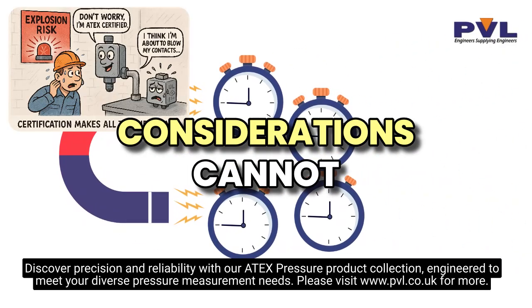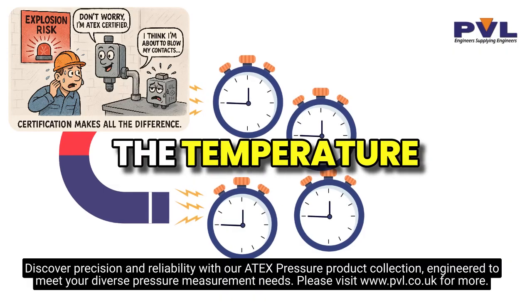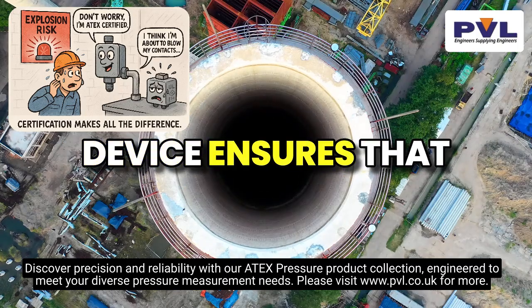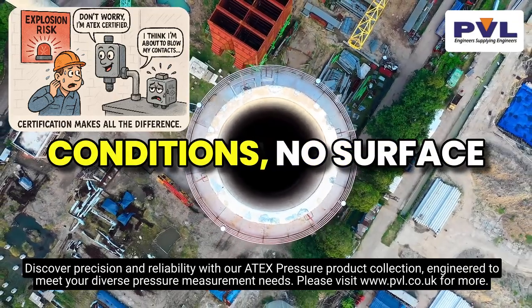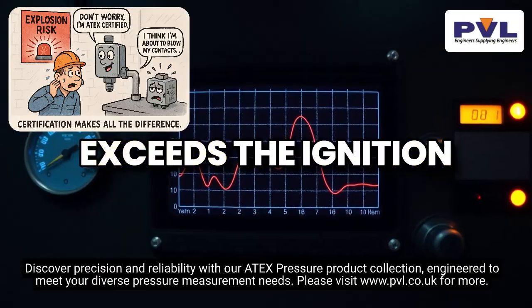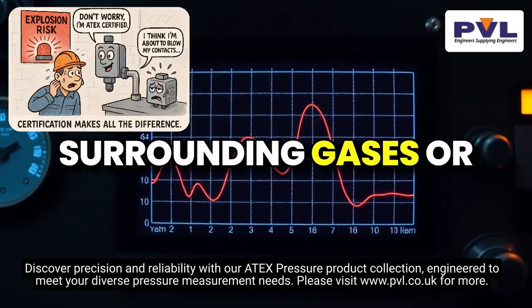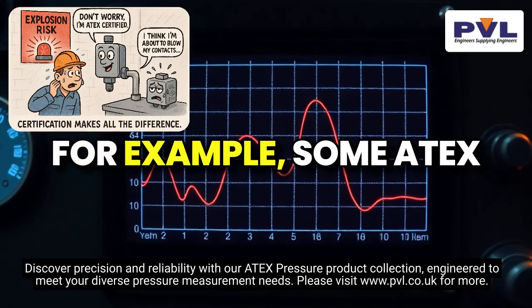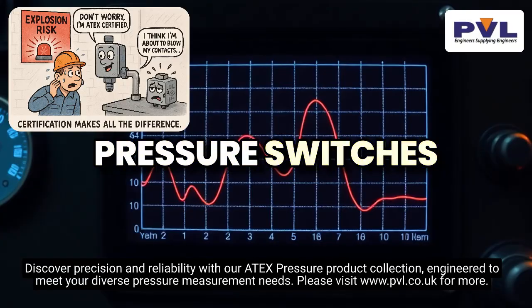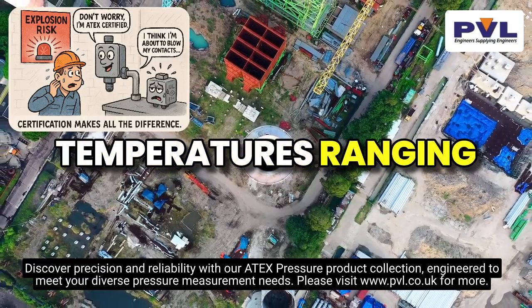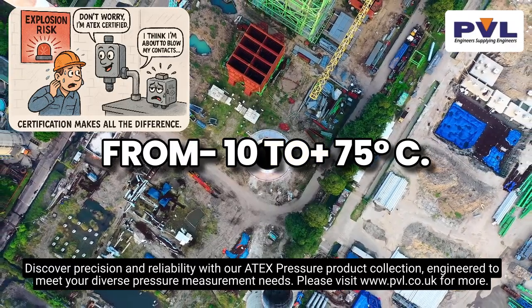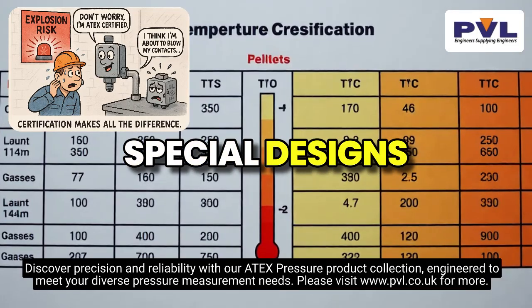Temperature considerations cannot be overlooked. The temperature classification of a device ensures that under the worst-case conditions, no surface exceeds the ignition temperature of the surrounding gases or dust. For example, some ATEX pressure switches can operate in ambient temperatures ranging from -10 to +75 degrees C. In extreme conditions, special designs may be necessary to maintain safety.